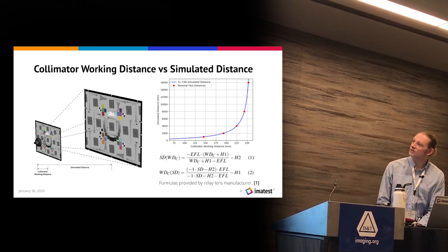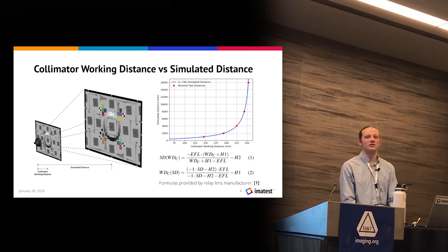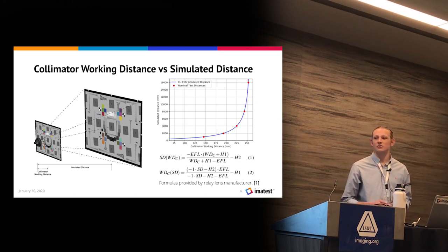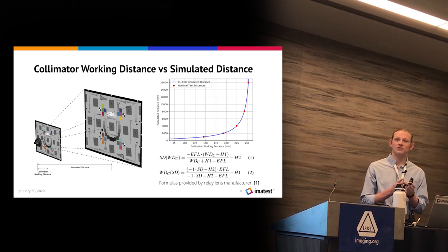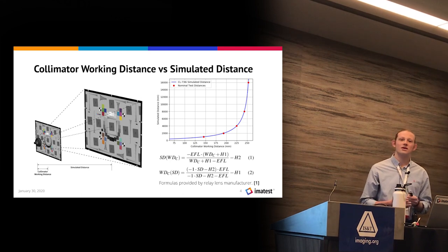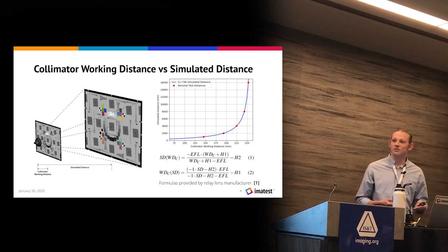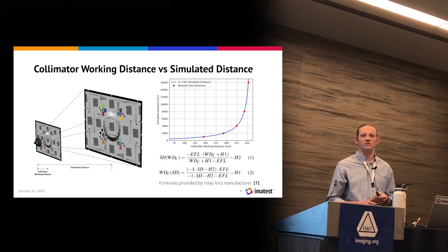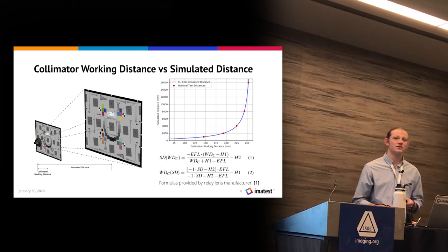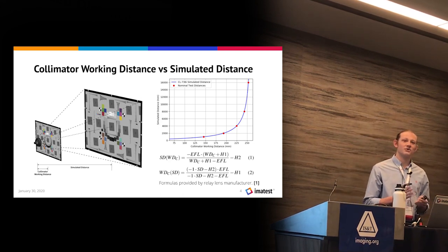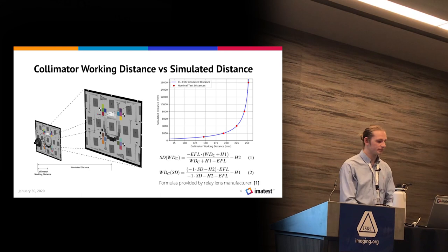In this test, we use the CL736i relay lens, which has an inspectable field of view of up to 70 degrees, meaning you can use a camera with up to 70 degrees field of view. The other relay lenses that work with this system have inspectable fields of view of up to 120 degrees. We've validated those lenses with the same process.